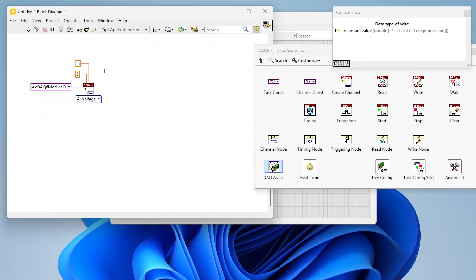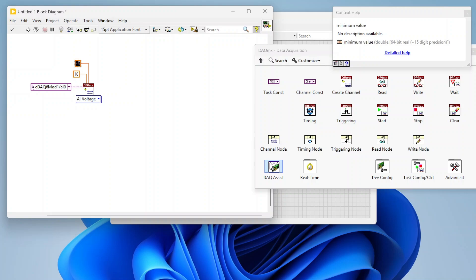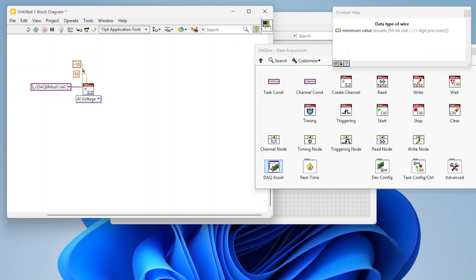Some DAQmx devices, like the NI9205 C-Series module, have multiple ADCs built in. Based on the min/max values you enter, DAQmx will pick the best ADC to use. If your signal goes up to 8 volts but you've set the range to ±5V, you'll only read the max value that the 5V ADC can handle. Set values that make sense for your hardware, as some devices only have a single ADC.